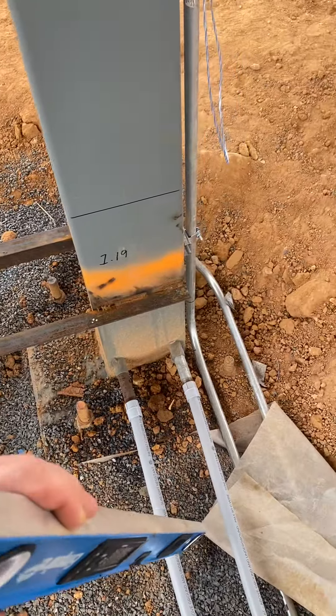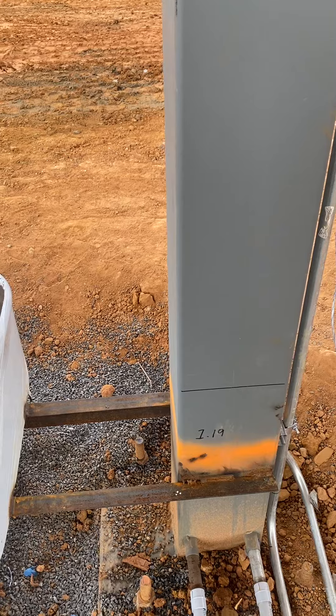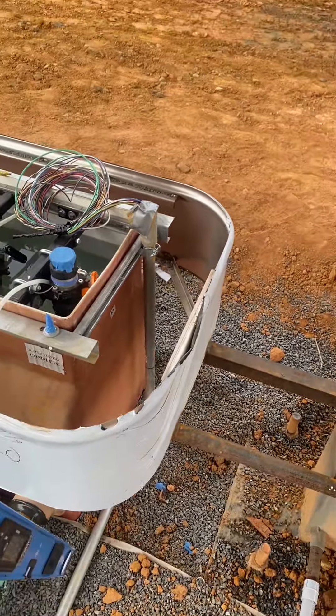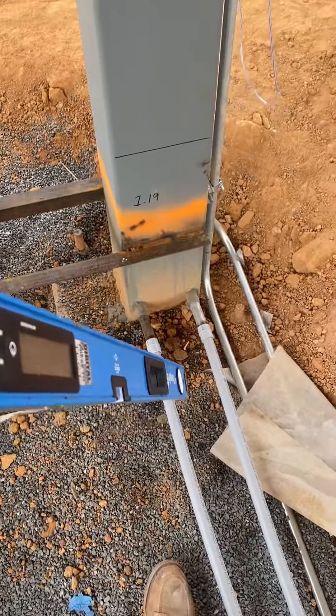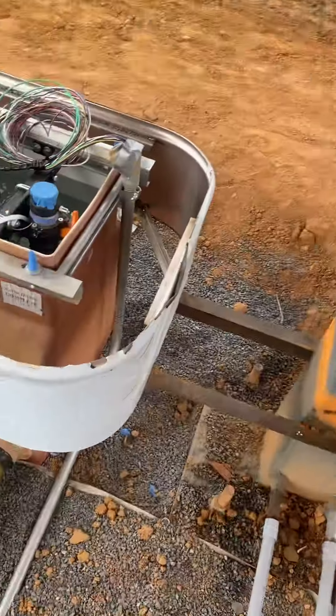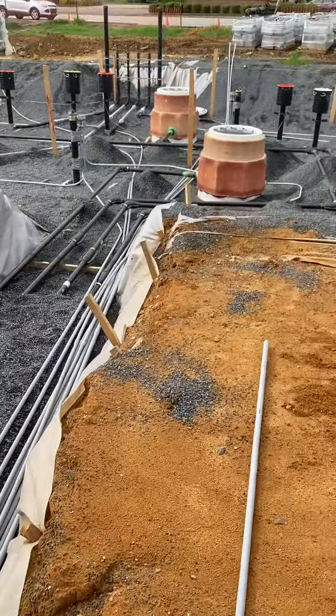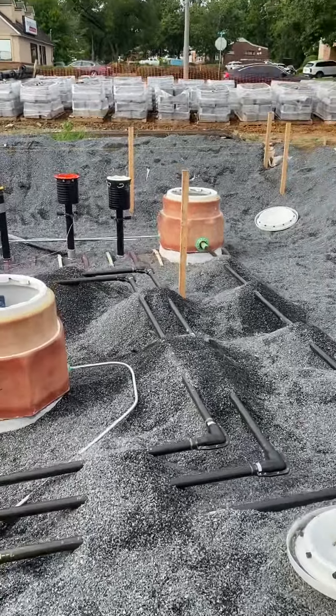You can run plastic if it is not part of the boundary area and doesn't enter into that boundary area. You can see here you've got your pumps, and then this is service conductors for the canopy. Coming along over here at your pumps, I want you to see where your pumps have a separate ground.